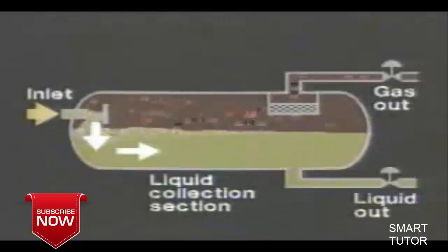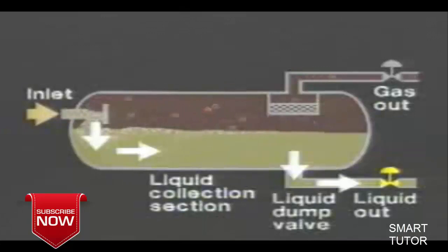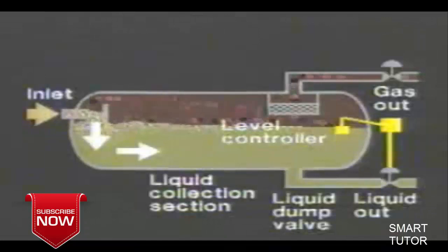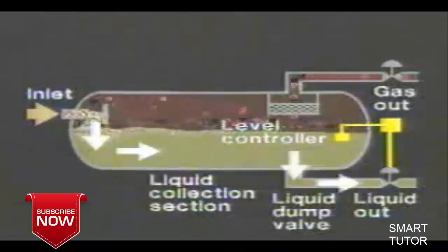The separated liquid then leaves the vessel through the liquid dump valve, which is regulated by a level controller. The level controller senses changes in liquid level and controls the dump valve accordingly.